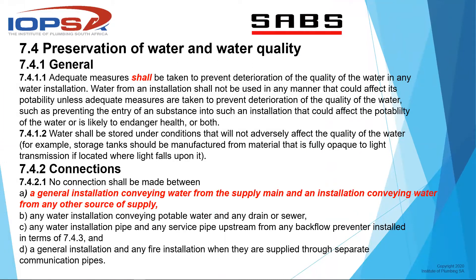In SANS 10252 Part 1, sub-section 7.4 covers preservation of water and water quality. Clause 7.4.1.1 states: adequate measures shall be taken to prevent deterioration of the quality of water - not 'should try' but a definite 'shall.' Clause 7.4.2 discusses connections, stating that a general installation conveying water from the supply main and an installation conveying water from any other source of supply must not be connected - there must be a physical break between downstream and upstream water.